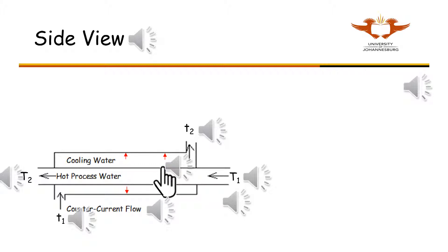However, the heat transfer area will need to increase to allow this, leading to an increase in heat exchanger cost. A difference of 5K between T2 and t2 is usually considered to reduce pumping costs without increasing heat exchanger capital cost too much.